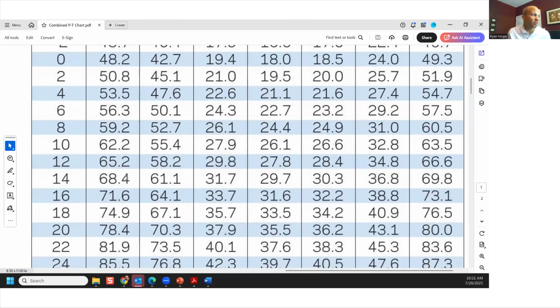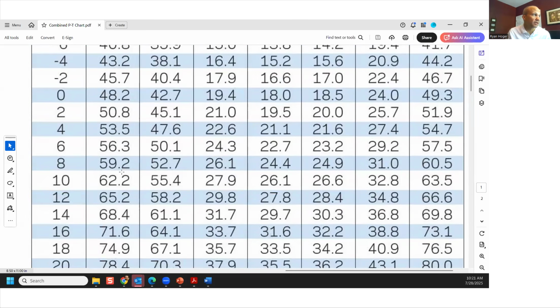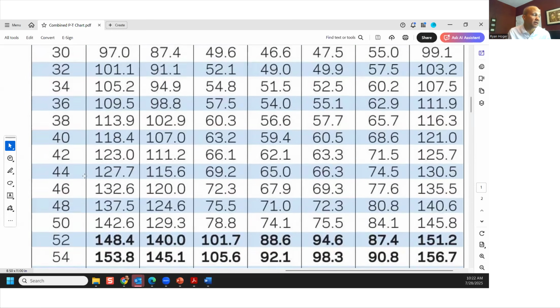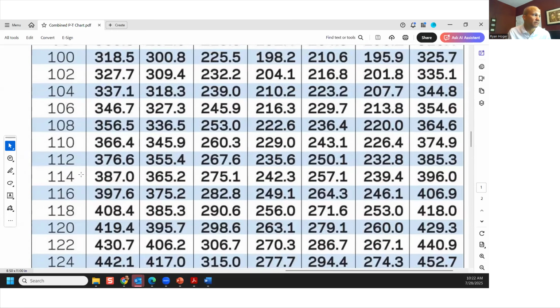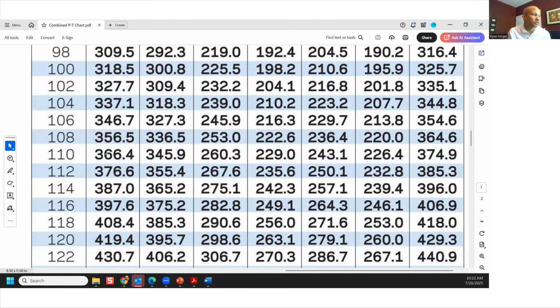If we go to something that's more normal, let's say we're operating at more like 45 degrees, R-454B would be 40 at that pressure, and R-32 would be 47 at that pressure. So these things are pretty similar. If I go way higher, let's go up here, 366. So 110 pressure, 366 degrees for 410A, 346 for 454B, 375 for R32. So R454B is going to be operating at a slightly lower pressure than R410A was. R32 will be at a slightly higher pressure, but they are in fact in the same general ballpark.